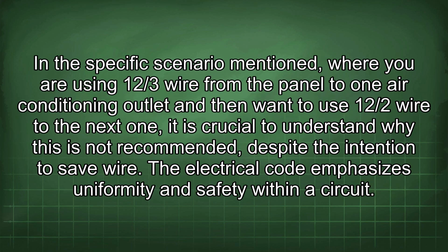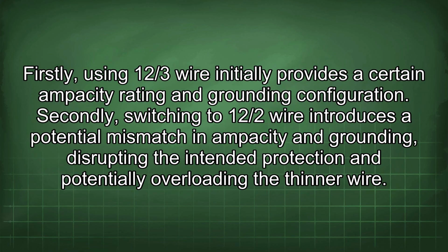In the specific scenario mentioned, where you are using 12/3 wire from the panel to one air conditioning outlet and then want to use 12/2 wire to the next one, it is crucial to understand why this is not recommended, despite the intention to save wire. The electrical code emphasizes uniformity and safety within a circuit. Firstly, using 12/3 wire initially provides a certain ampacity rating and grounding configuration.